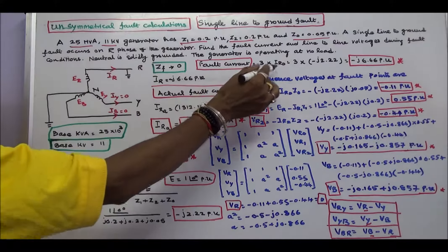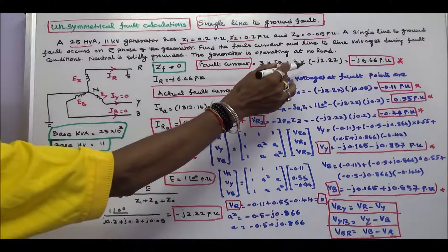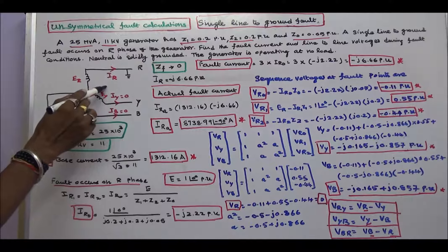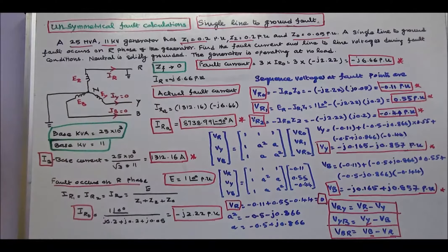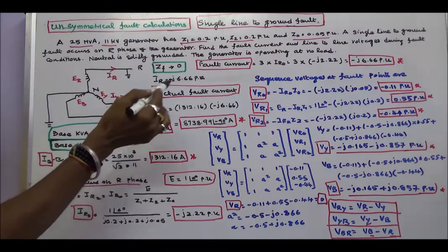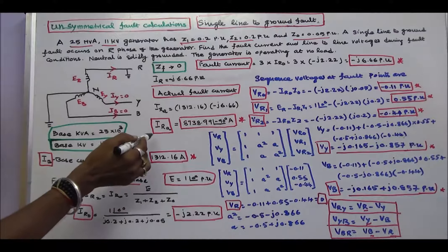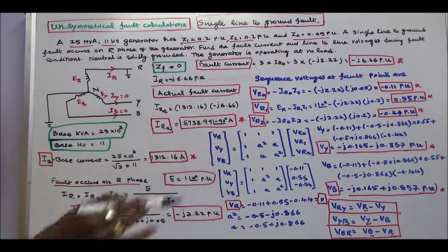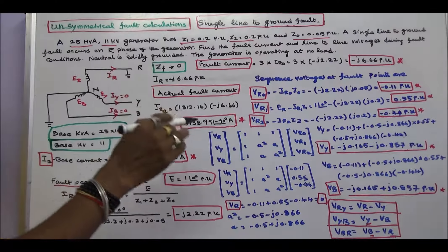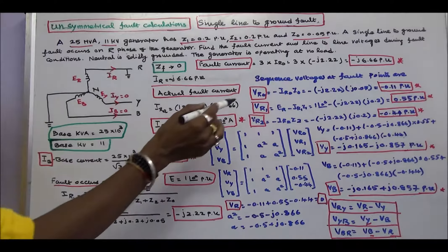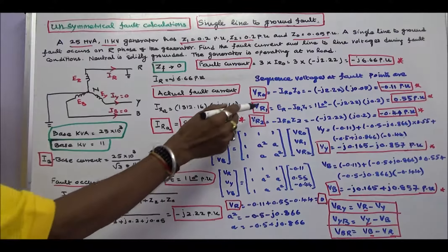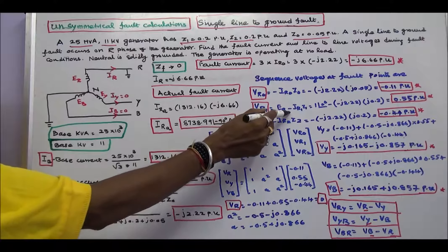The fault current is three times the zero sequence current: 3 into minus j 2.22, which equals minus j 6.66 per unit. Therefore the fault current IR equals minus j 6.66 per unit. Knowing the base current, the actual fault current IR equals base current multiplied by per unit current, giving 8738.99 angle minus 90 degrees amps.